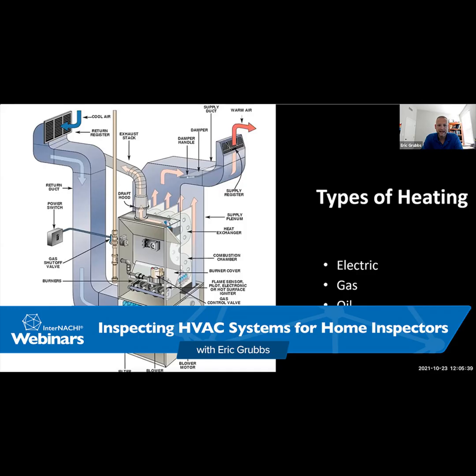Along with burners, ignition systems are going to be different depending on what kind of system it is and how old that system is. You have these different types, especially standing pilots. A standing pilot system just has an additional line off the gas valve that supplies gas to a port that typically has a flame burning on it at all times. It's a small little flame, and when they get that call for heat, it uses that flame to ignite those burner ports. Again, you won't see these except on older equipment or water heater type systems.